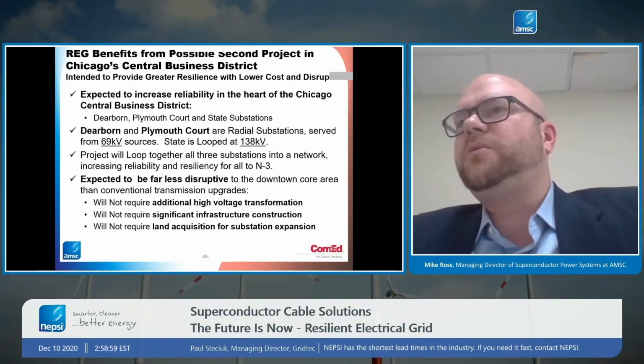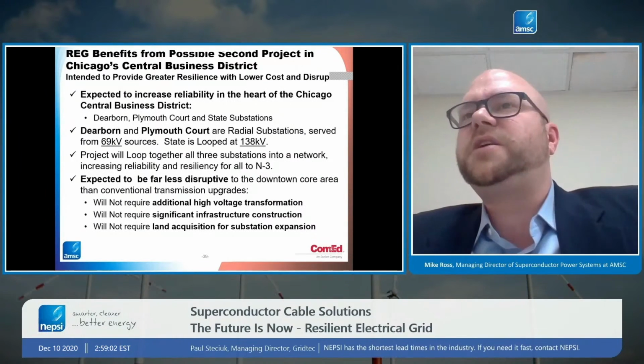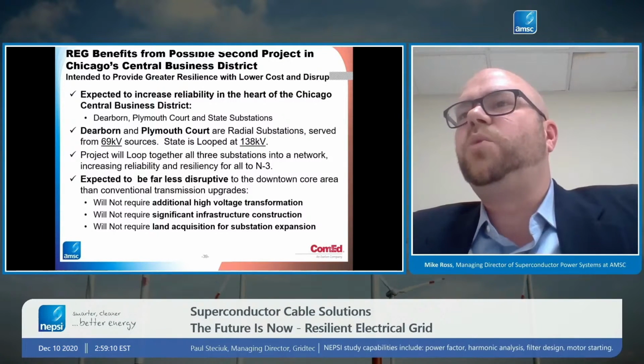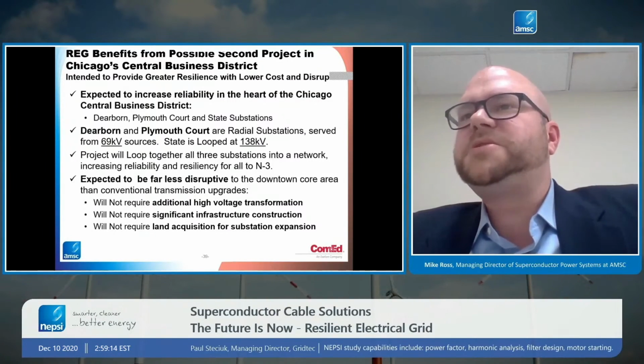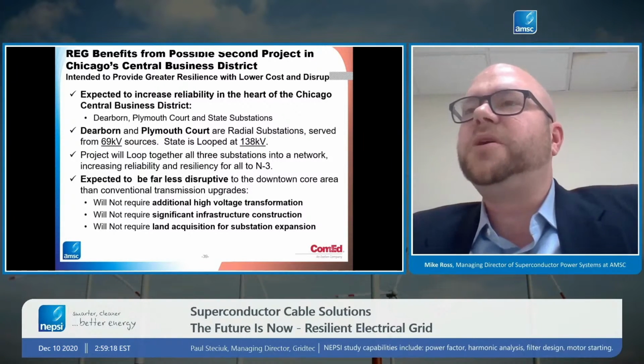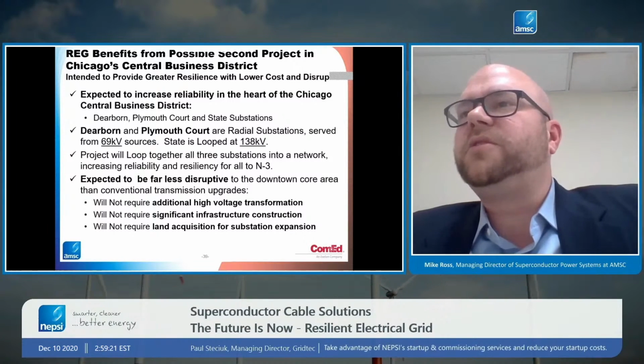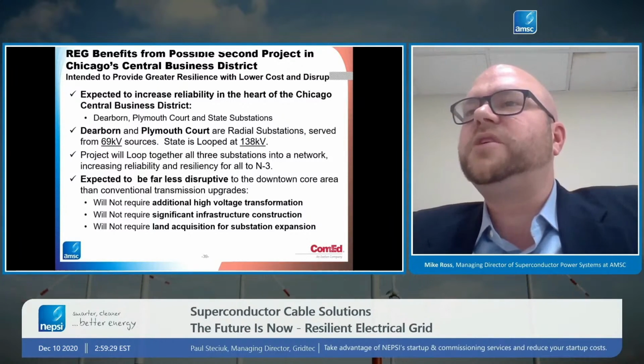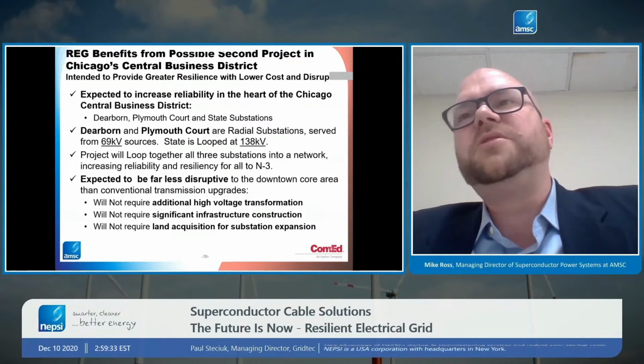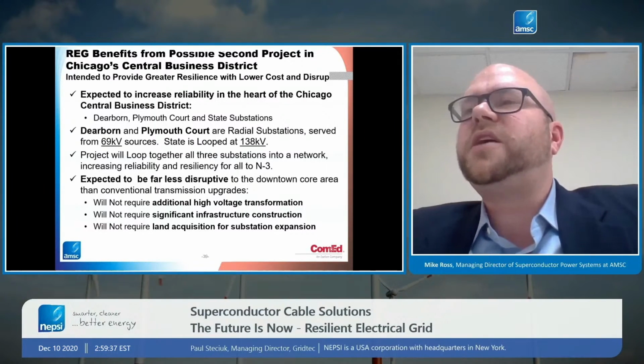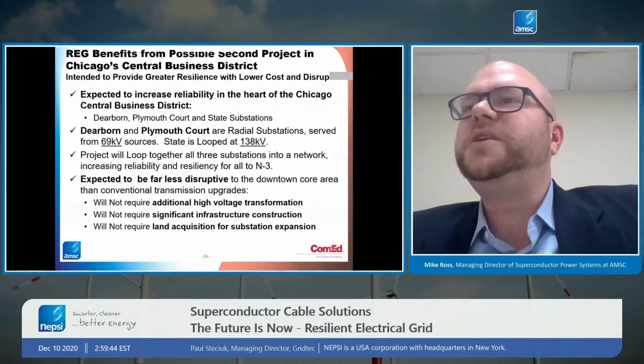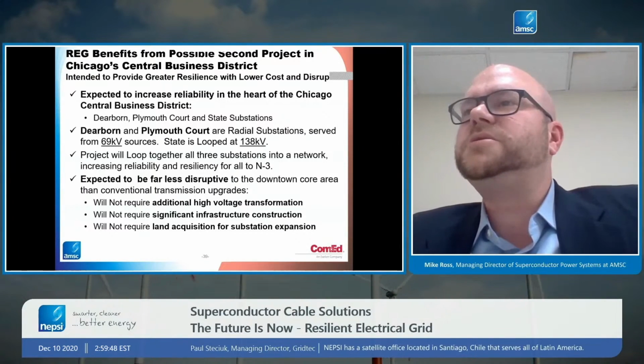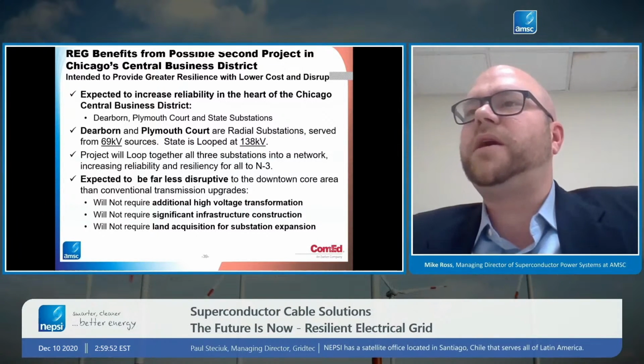The basic project that we're executing in Chicago, the phase 2 of the project, will involve interconnecting 3 substations together. 2 of those substations are at 69 kV and 1 is at 138 kV. When we loop those substations together, we'll be able to bring the reliability level of downtown Chicago up from its current level of N-2 to N-3. So what that means is today, they can lose any 2 transmission components and still be able to serve their load. But when the system's installed, they'll be able to lose 3 components, so an entire another level of redundancy without losing power. And that's what resiliency is all about, increasing the reliability so that you can lose larger components of the system without having a blackout.